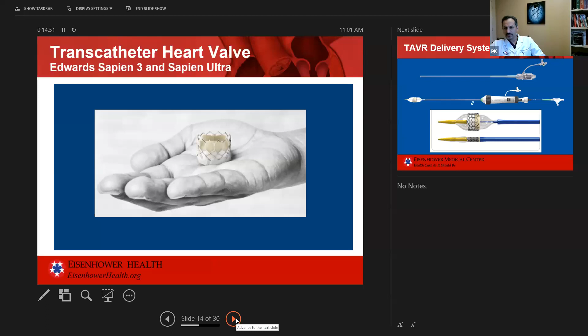Now, obviously, when we deliver this valve, it doesn't look like that. What we do is we crimp this valve down so that it is smaller in size. And this is what our delivery systems look like. So we have this large tube, and this is about 45 centimeters long. So, about 18 inches, maybe 15 inches long. It goes in from the groin all the way up to the abdomen. That's the tube through which the valve is inserted. This is the delivery system of the valve.